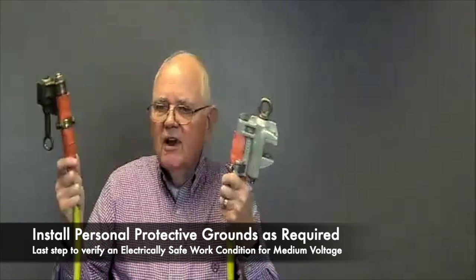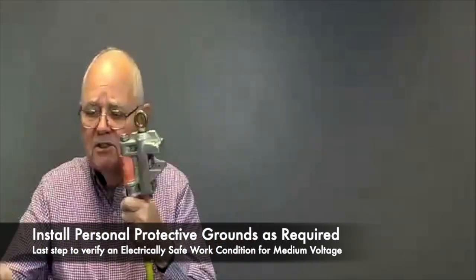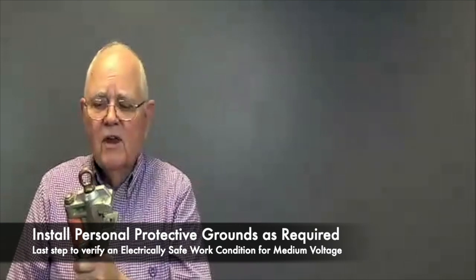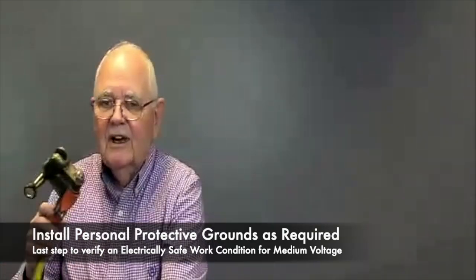Now, these particular grounds, I'm going to have one just for the ground clamp. And if I don't have to actually attach it to bus work, what I have installed in much of my modern switchgear now is I'll have a ball already mounted on the grounding bus. And then this is just like a trailer hitch. I just put this over the ball and then I tighten it down. And then that gives me a good firm connection to ground. Then I want to make sure that I'm using my live line tool.